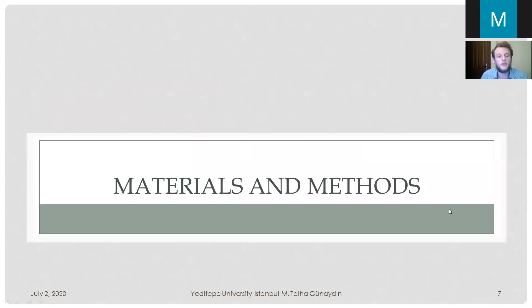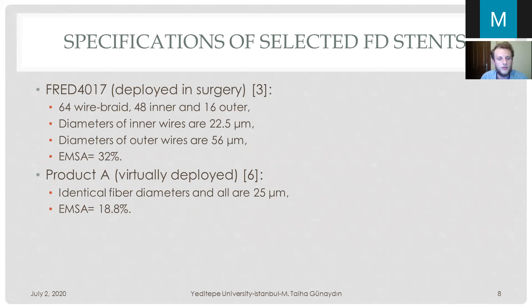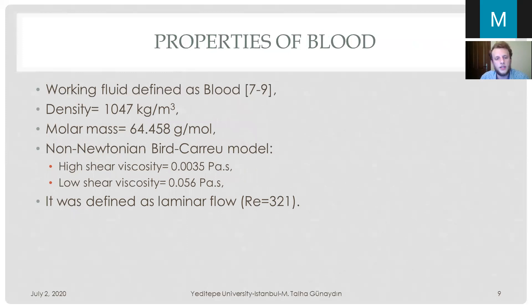For this study, two flow diverter stents were chosen. The first is FRED-4017, which was used in surgery. It has a 64-wire braid configuration: 48 wires with a diameter of 22.5 micrometers and 16 wires with a diameter of 56 micrometers. The other flow diverter stent was Product A, which unlike the other has identical fiber diameters — all 25 micrometers — and an EMSA value of 18.8%. For the working fluid, blood was chosen and defined as a non-Newtonian Bird-Carreau model with specified low and high shear viscosity values.